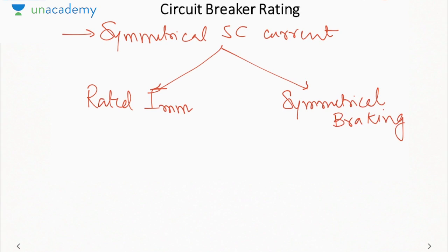So here, once we have I symmetrical, we will multiply it by 1.6. That will be the rated momentary current of the circuit breaker. That means the momentary current, the current that exists for a short duration, can exist only up to this much value. The short duration current should not exceed this value. That is your rated momentary current.